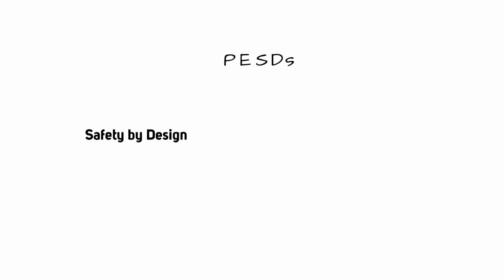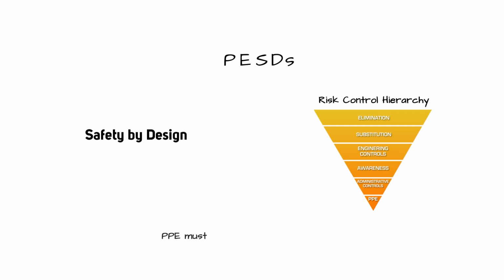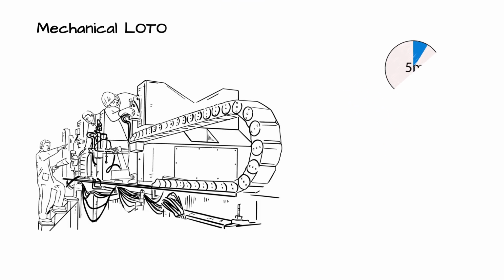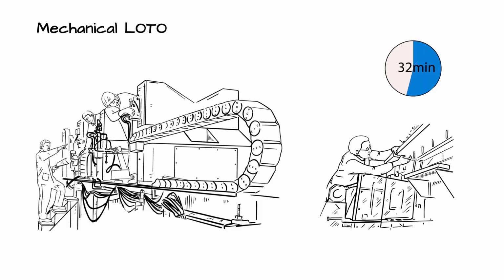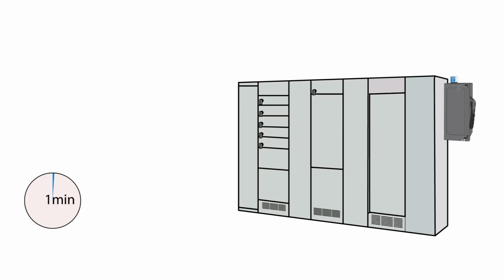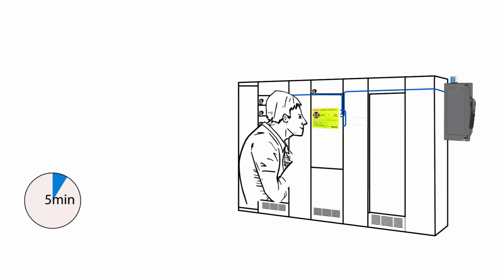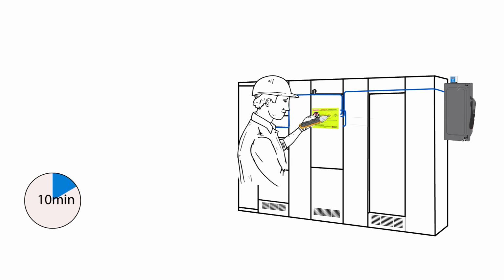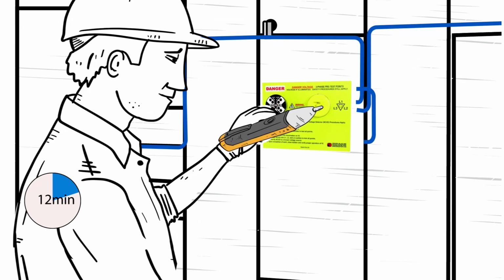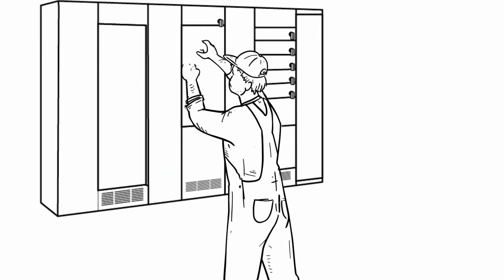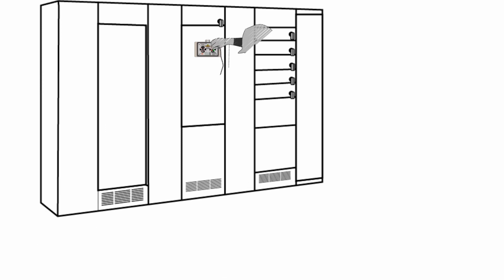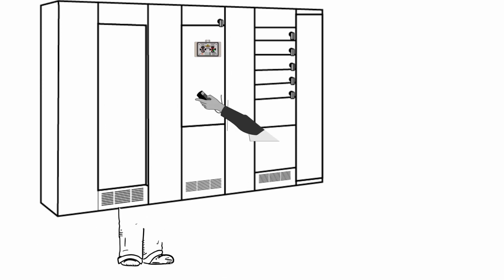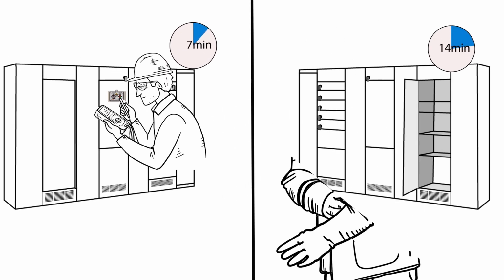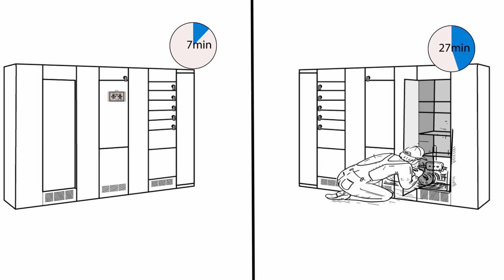Permanent Electrical Safety Devices, or PESDs, combine the electrical safety by design principles outlined in the risk control hierarchy and are applied to either eliminate the risk or reduce the risk to a minimum acceptable level while performing lockout-tagout tasks. PESDs are electrical components that are permanently installed into electrical systems by hardwiring them directly to the source of voltage. These devices enable electricians or maintenance workers to validate the presence or absence of voltage from outside the electrical cabinet door without ever being exposed to hazardous energy inside the door. PESDs, combined with risk-certified procedures and drafted by a certified safety professional, enable a safer and more productive lockout-tagout.